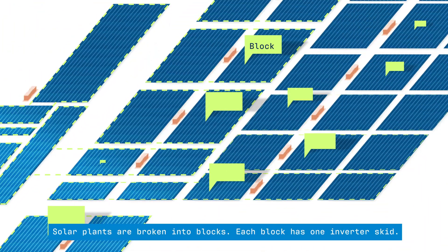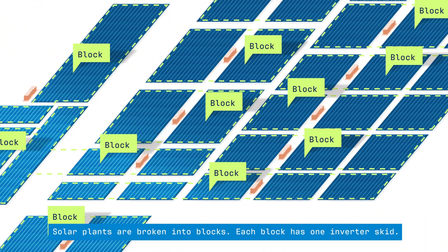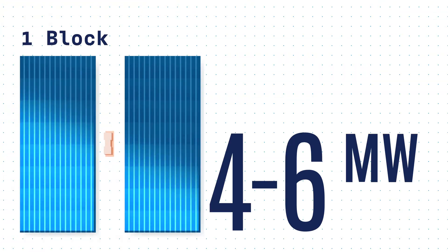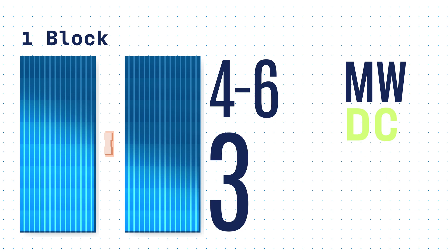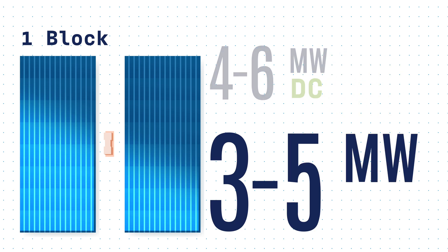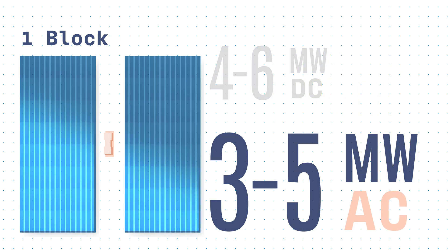Solar plants are broken into blocks. Each block has one inverter skid. Usually, a block provides 4–6 megawatts of DC and 3–5 megawatts of AC power.